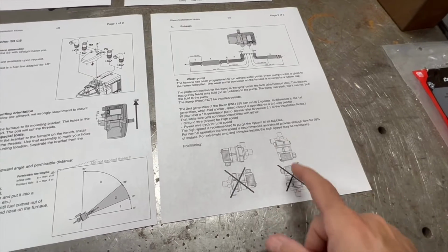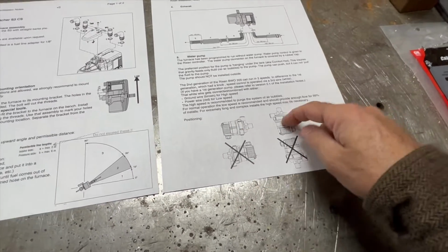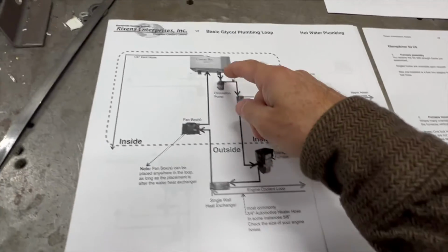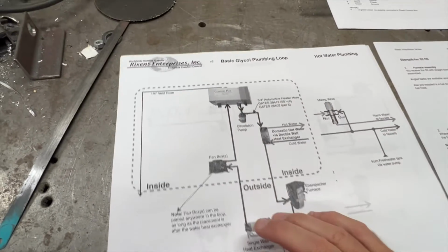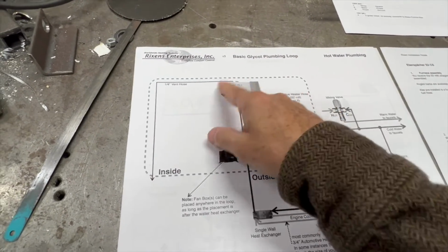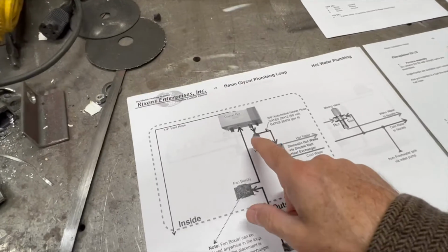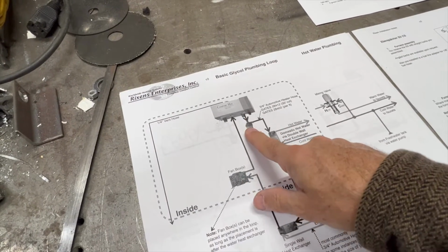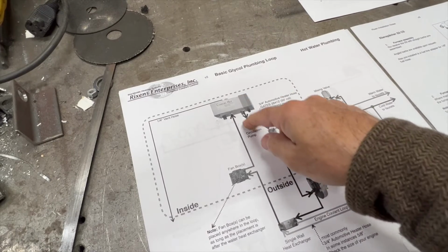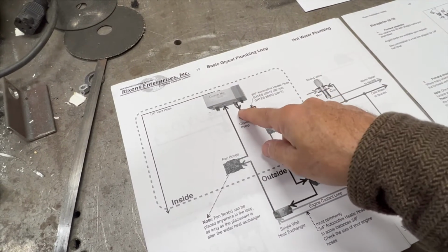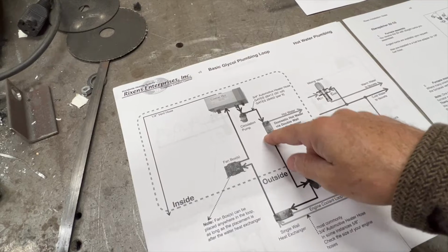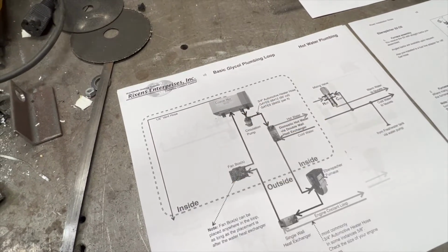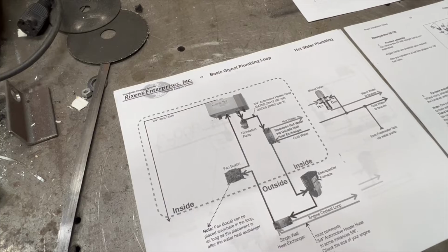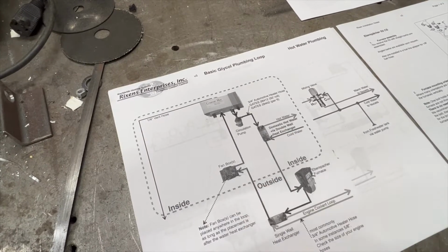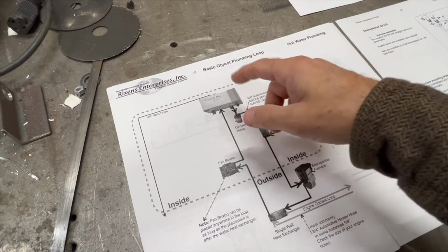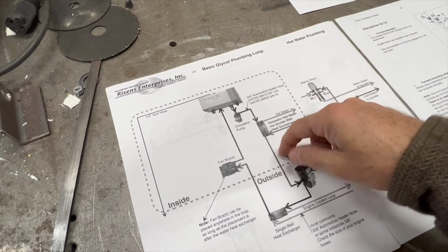Something interesting about the water pump: different orientations are possible. We're going to mount ours this way because it'll be right underneath the Comfort Hot expansion tank. Supposedly this pump doesn't suction, it only pumps, so we need it on this side so gravity brings the water out and pushes it through. This way it can make pressure on this side, but it doesn't pull water. In contrast, the water pump we use for pressurizing our domestic water can pull water.